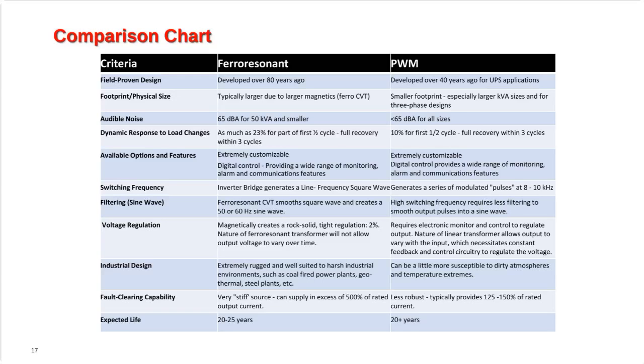It tells you the differences between the two. So for a Ferroresonant system, they were developed over 80 years ago. So they have a huge amount of history behind them. They've been in the field for 80 years and are very robust. PWM was developed over 40 years ago. So it's only half the age of the Ferroresonant technology. It's robust, but it hasn't been around for anywhere near as long. For a Ferroresonant system, the footprint or the physical size of the UPS is typically larger due to the larger magnetics, the Ferroresonant constant voltage transformer. PWM has a smaller footprint, especially as you get up into the larger kVA sizes and also for three-phase designs.